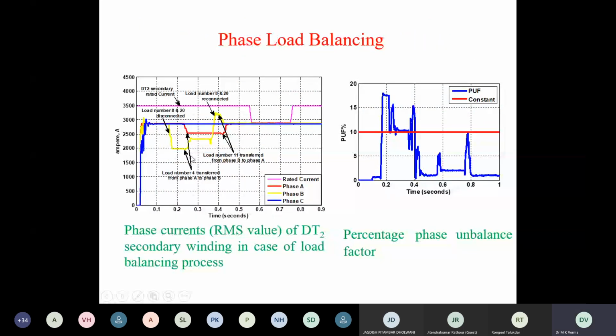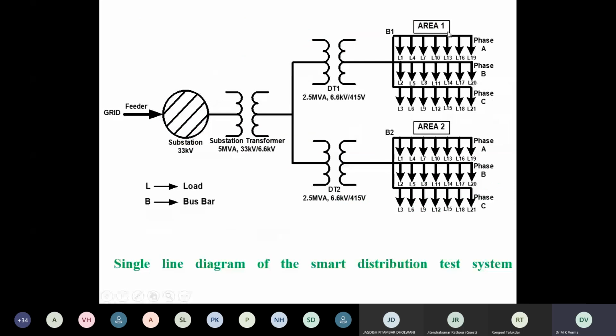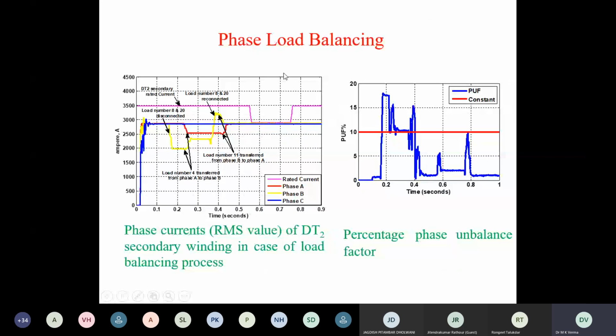Load number 4 is transferred from phase A to phase B to make it balanced. Load number 4 was connected on phase A. Now it is shifted to phase B to make the system balanced. So the load balancing algorithm was run, and then load number 4 is shifted from phase A to phase B. That makes it balanced. The phase unbalancing factor comes within the limit, less than 10%. Then again at some time it becomes unbalanced, and in the same way the balancing is done.